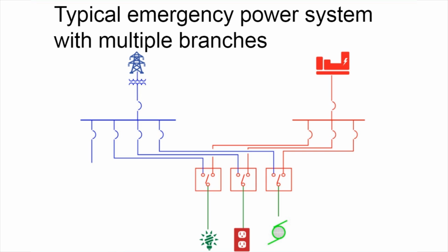All of that's not to say that more transfer switches should not be added to the system. Additional transfer switches can be a very effective method to distribute the load to multiple smaller feeders and minimize the risk of a single transfer switch failure causing a widespread outage. It can also be a very effective approach to add more load to the EPS with the capability of systematically shedding the least critical equipment in the event of an overload.